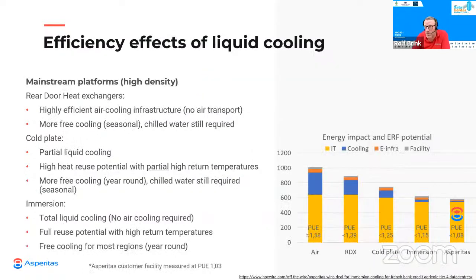This becomes clear when looking at the more explicit effects of liquid cooling strategies. Rear door heat exchangers are very efficient due to the usage of water as the main coolant circulation throughout the facility. It is, after all, easier to exchange heat with water than it is with air.